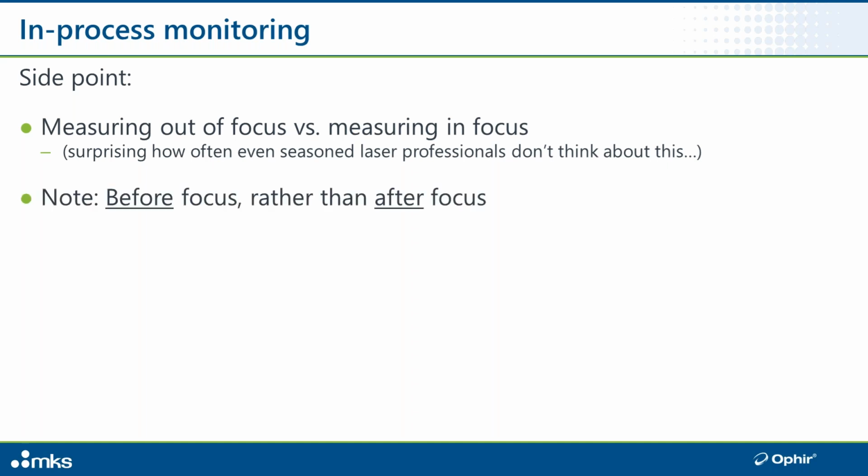And just as a side point, but an interesting one, not everyone knows that all other things being equal, where practical, it's preferable to measure before focus rather than after focus, as I thought this was very cool. At the focal spot, there may sometimes be losses caused by photoacoustic shockwave effects. All right, tell me that's not cool.